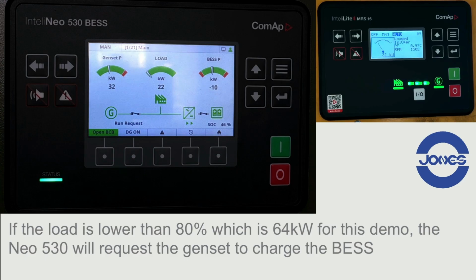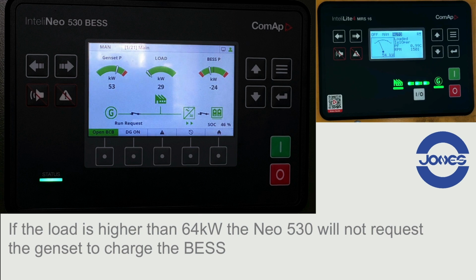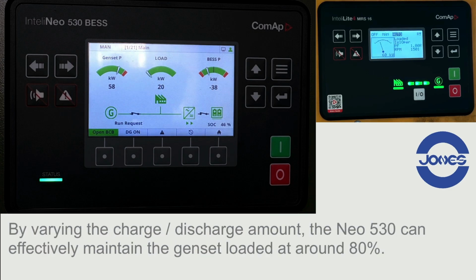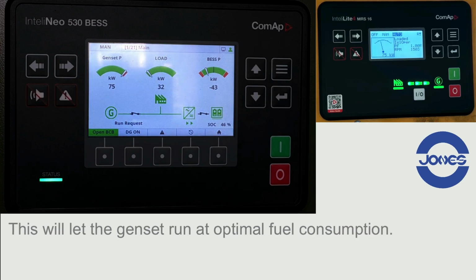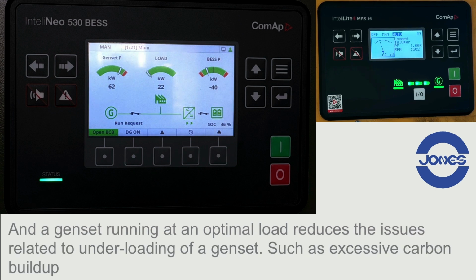If the load is lower than 80%, which is 64 kilowatts for this demo, the Neo 530 will request the genset to charge the BESS. If the load is higher than 64 kilowatts, the Neo 530 will not request the genset to charge the BESS. By varying the charge-discharge amount, the Neo 530 can effectively maintain the genset loaded at around 80%. This will let the genset run at optimal fuel consumption. And the genset running at an optimal load reduces the issues related to underloading of a genset, such as excessive carbon buildup.